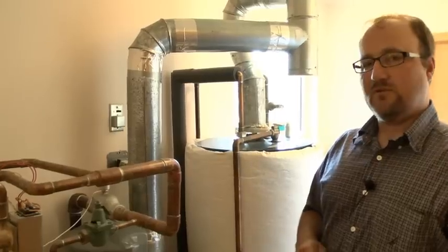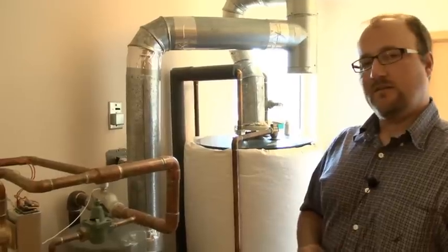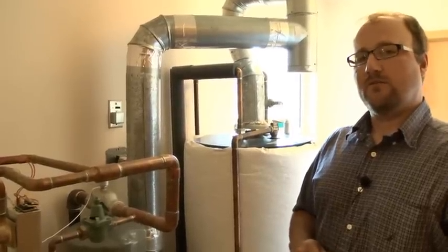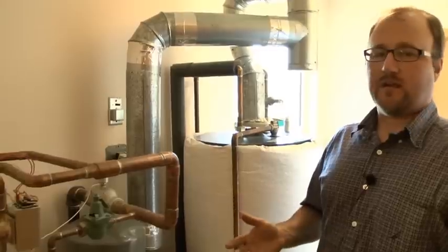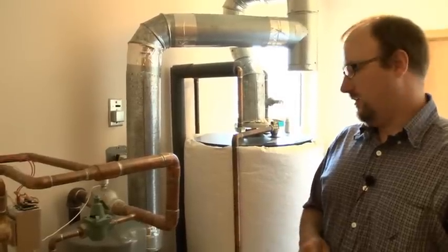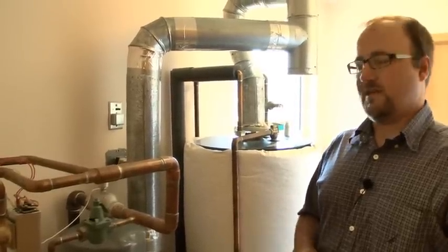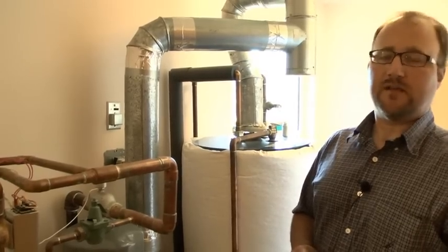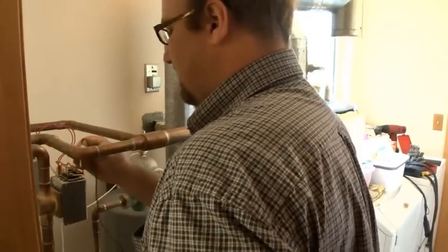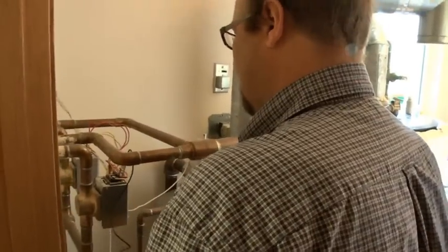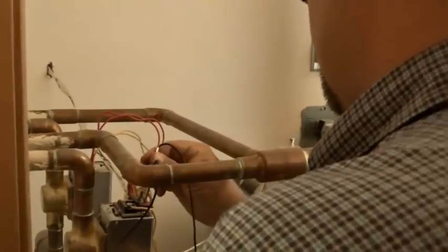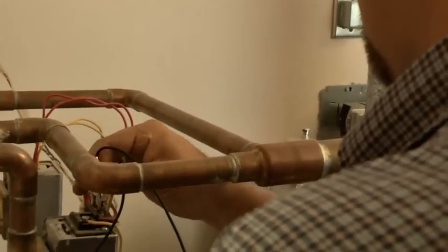If more fuel is being supplied to the appliance, then there's a good chance that our orifices are too big, or maybe our gas pressure is too high. And what occurs then is we start creating carbon monoxide. We have a bad burn. We'll go ahead and get this appliance to fire, and then we'll go out and look at the gas meter and clock it.